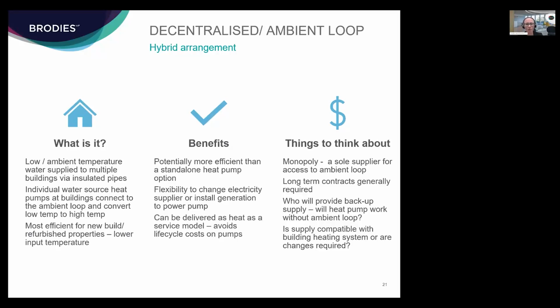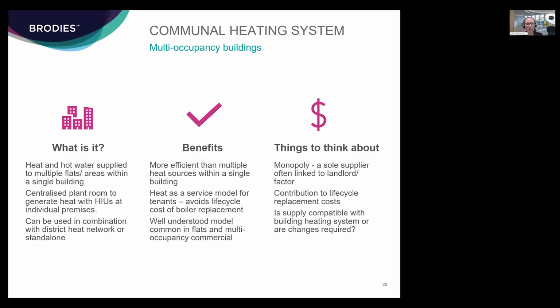So then moving on to a communal heating system. This is now hopefully a bit more familiar territory. This is where heat and hot water are supplied to multiple flats or multiple offices within a single building. You have a centralised plant room to generate the heat with HIUs, heat interface units, at individual premises. This can be combined with a district heat network if you wanted, so you can have the connection coming into the plant room and then supply it around the building, or it can be a standalone solution.